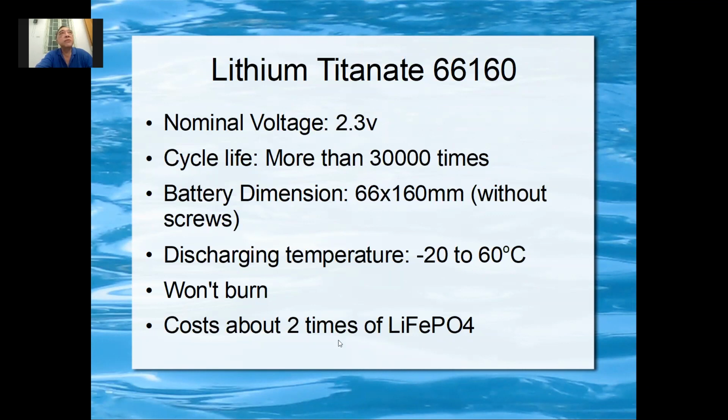Okay. So one good thing is you can drill a hole right through. You can chop it into two pieces and it won't burn. Unlike lithium ion battery, it will not burn. But it costs, let's say, 2 times lithium iron phosphate. Okay, lithium iron phosphate battery and lithium ion are about the same price, similar. So in the long term, it's still better because 2 times and you get a cycle of 30,000 times. Practically, you don't need to replace your battery.